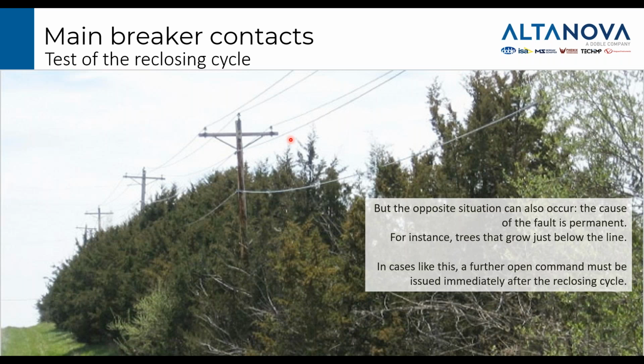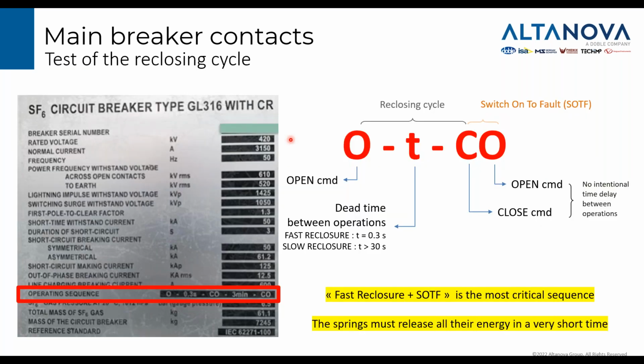But there is also the opposite situation. The fault will not disappear, but remains. In this case, after the circuit breaker tried to close, for sure there will again be the fault current flowing, and then a second open command must be issued. For this reason, on the nameplate of the circuit breaker, you will find an indication like this: operating sequence.